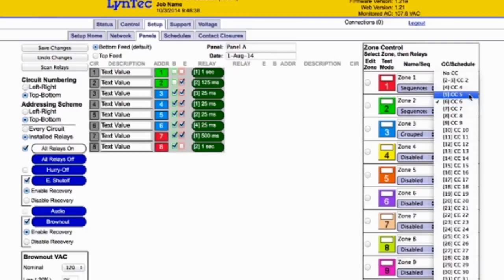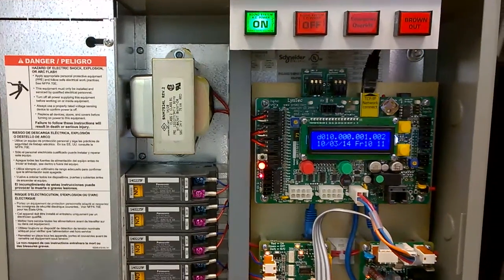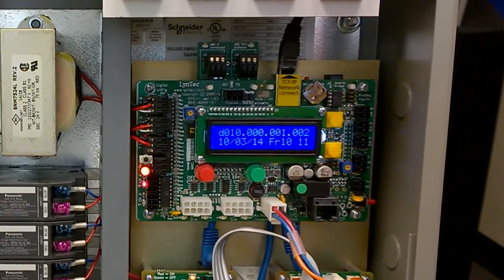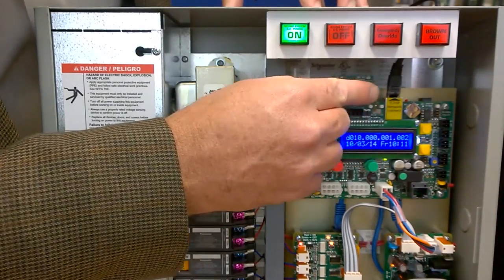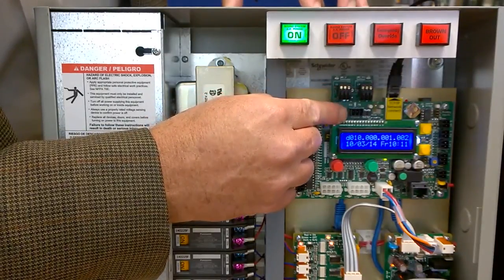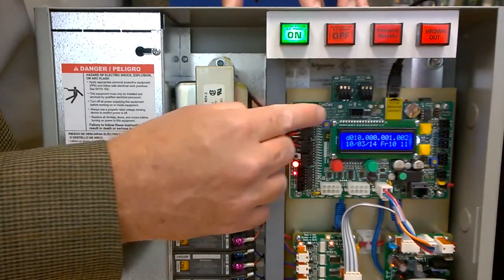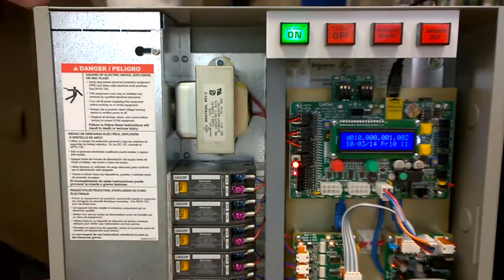IP control, browser control over any smart device or a computer with a browser, contact closure control, including optical or occupancy sensors, and built-in scheduling timers, all included in the onboard controller. No other system has more self-contained control options. In addition, if you'd like to use a third-party master control system to control your RPCR, no sweat. The Lyntec RPC controller comes standard with interfaces for IP, DMX, RS-232, streaming ACN, and of course your contact closure inputs. All these interfaces are preloaded.